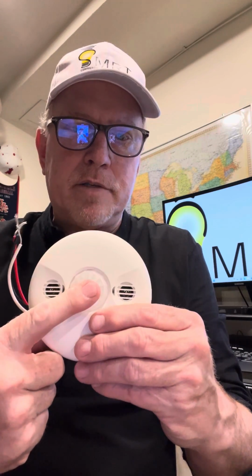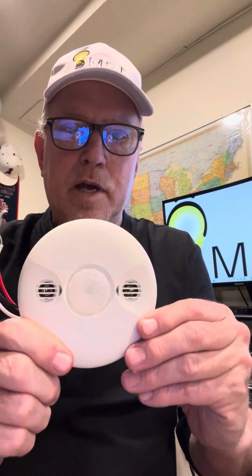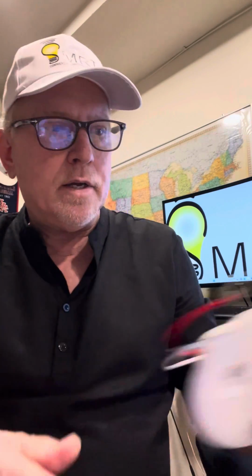The second of three components, you're more than likely going to want some type of sensor on the project. We have all sorts of different sensors: low voltage sensors, wall sensors, dual tech, passive infrared. This particular one is a line voltage, Bluetooth, passive infrared and ultrasonic sensor. We call that dual technology because there are two technologies. Passive infrared is the primary, first technology, that's your major motion. Ultrasonic is your second technology, that's your minor motion. So you're going to have some type of ceiling sensor in that space.